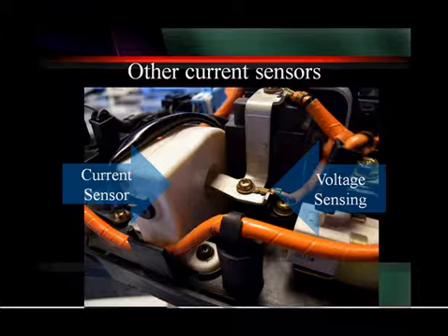What you're going to understand, in our next class on hybrids, we're going to get down to the nitty-gritty of all these different voltages and currents that are being sensed inside these controllers. The reason for doing that is so that you never have to come in here and put a voltmeter where that voltage sense lead is right there. You'd have to have rubber suits, rubber gloves, safety materials in order to get into this inverter and go there.